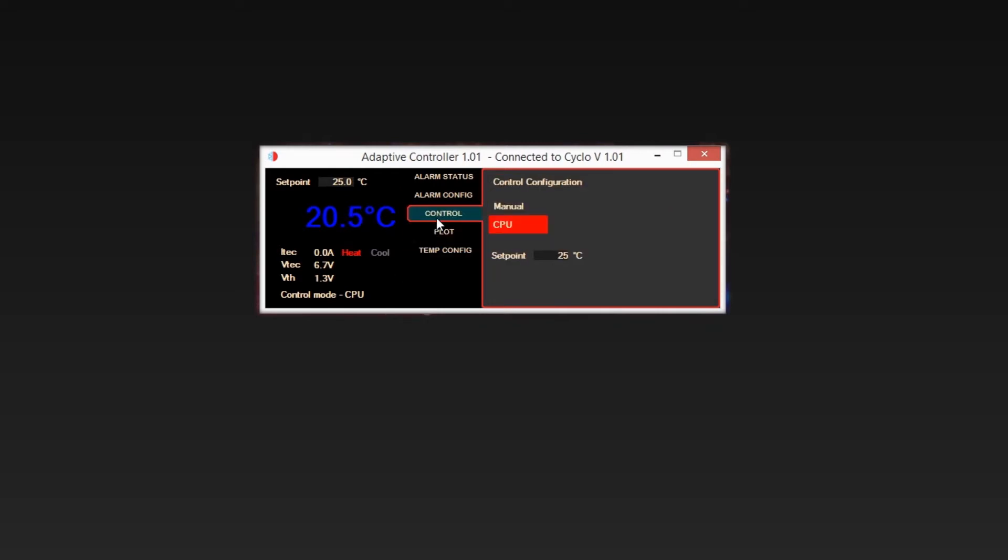Control tab. To control the set points via the HMI, you must set the jumper on the Cyclo board to CPU mode. Then, in the HMI, select CPU mode. This will then enable the set point field.